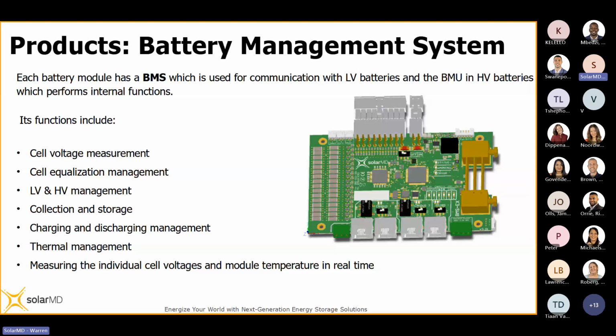The BMS also handles the rate at which the battery is charged during the charging process, and it may increase or decrease those values as the batteries reach a full state of charge or are reaching the bottom end where they are depleted. The BMS will adjust the amperage that the inverter is allowed to use. The battery doesn't tell the inverter explicitly what to do, but it sends its limits via the BMS, saying charge me at maximum rate or don't charge me any further, and the inverter should adhere to that guidance. However, if the inverter doesn't do that, the battery will kick in its self-protection mechanisms and open the relay, protecting the cells from damage. So the BMS has a very important role with lithium iron phosphate storage, preventing damage to the cells from being overcharged or discharged too far.